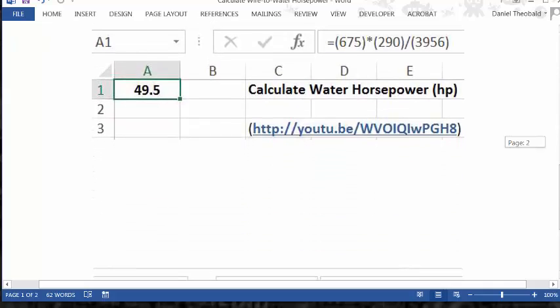Now let's remember this 49.5 and look at the calculation for the brake horsepower, which uses the water horsepower calculation, the 49.5, and then uses the pump efficiency divided by 100, which is the decimal equivalent of the pump efficiency. That gives us 67.4 brake horsepower.